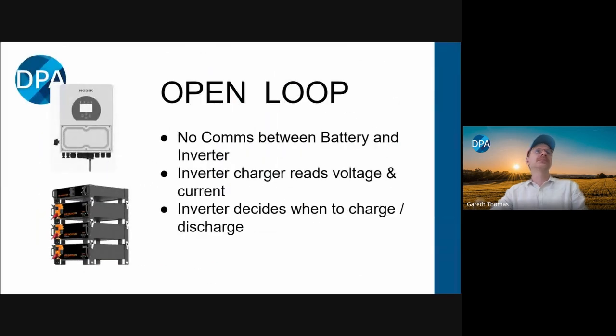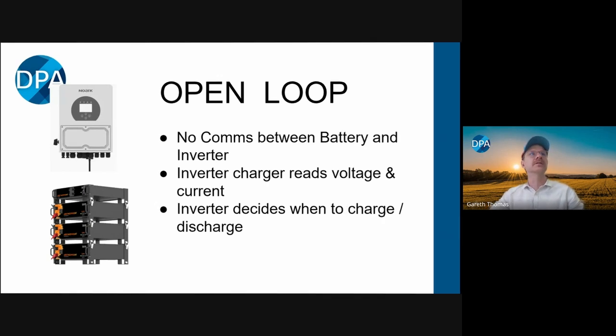So open loop means there's no comms between the battery and the inverter. The inverter charger just reads the voltage and current itself, and it decides when to charge and when to discharge. So most of us will be familiar with that. That's just like a normal lead acid type setup, and you've just got a fixed value for the current that you charge the battery at. And that's fine and works pretty well for most circumstances.